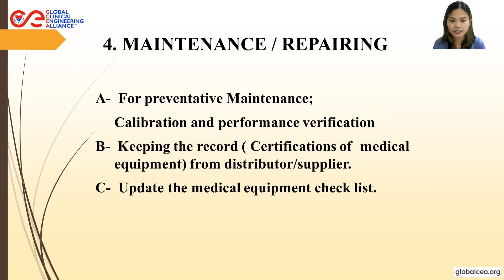Next slide is number 4, maintenance and repairing. For preventive maintenance, we provide calibration and performance verification and keep the records, certification of medical equipment from the distributor and supplier, and then we update the medical equipment checklist. Next slide, please. As corrective maintenance or repairing, we attend to and check all survey requests from the respective departments, and then handle and make decisions for repairing all medical devices and equipment. We collect data from the complaint register and work report.